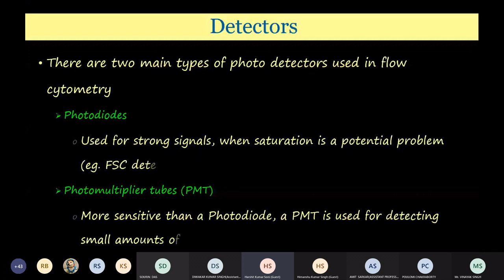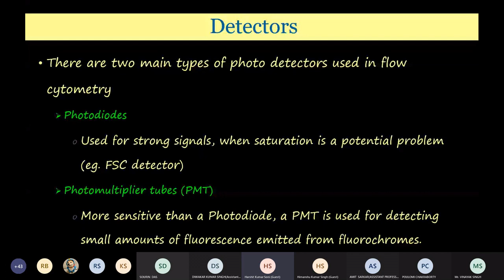Wherever we have a sensitivity problem, there we use PMT. When we have a very small amount of light coming and we want it to be detected, we use photomultiplier tubes. They are more sensitive than photodiodes and can detect a very small amount of fluorescence. You all know how a photomultiplier tube works. It has a photocathode and dynodes, and as the incoming photon comes, it will excite further electrons. Then a multiple chain goes on: one excites two, two excite four, and this is where you amplify your entire light signal. So you have very little light coming, but when it exits, it will have a very high intensity.